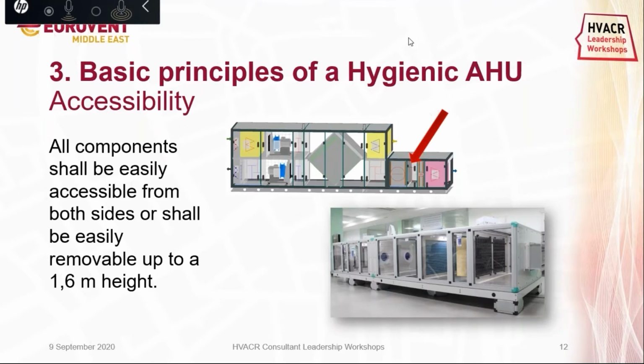Accessibility. When we say accessibility, what we mean is that all components in the unit shall be easily accessible from both sides and shall be easily removable without a big effort up to a certain height of 1.6 meters per section. On the screen, you can see an inspection section is added in between the cooling coil and heating coil, allowing the service people to reach coils easily for inspection and cleaning purposes.